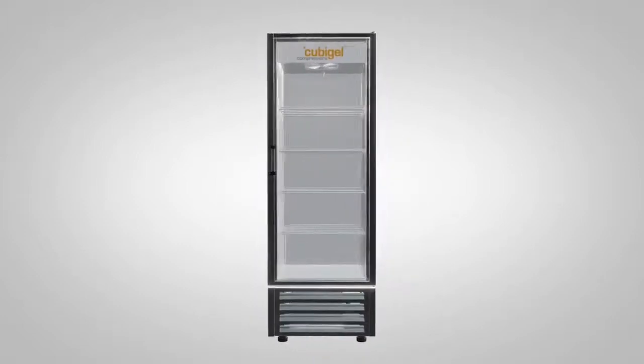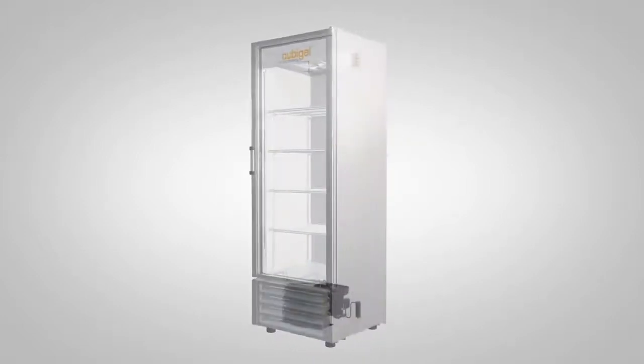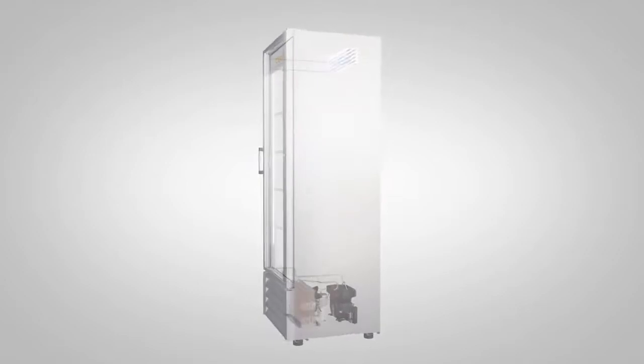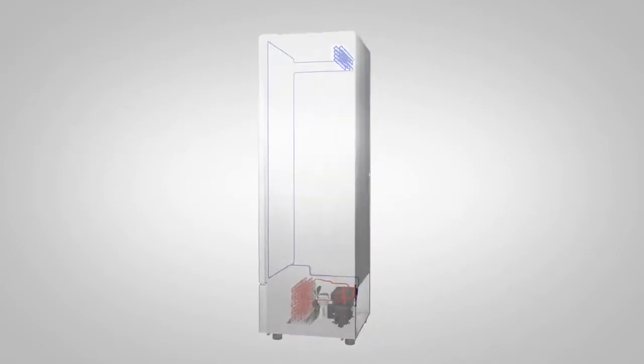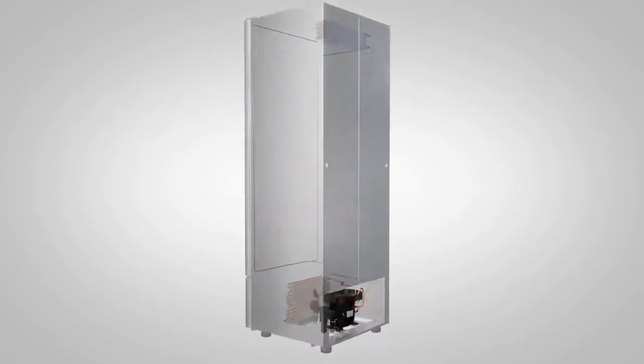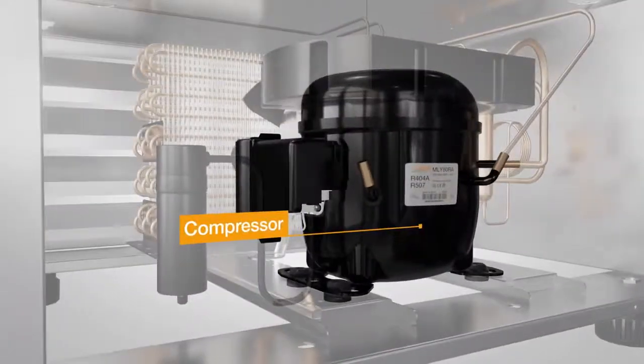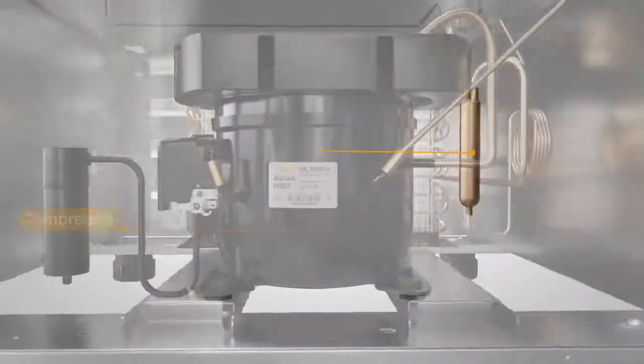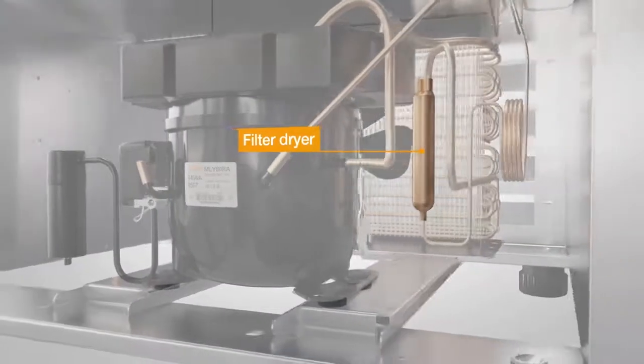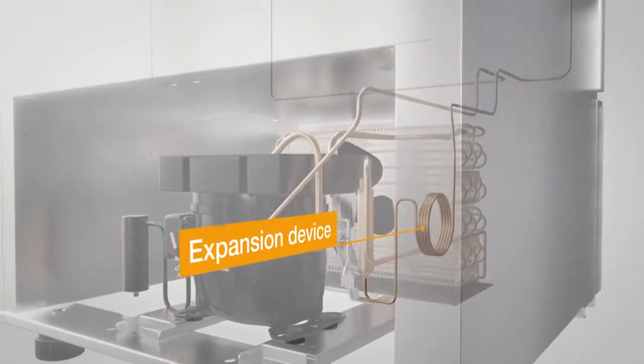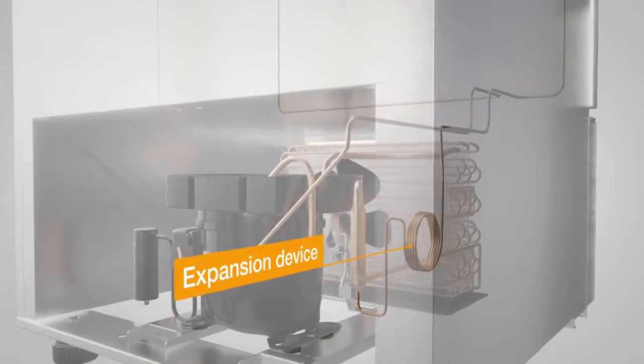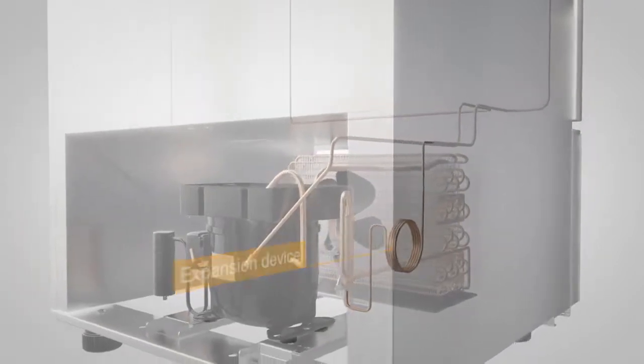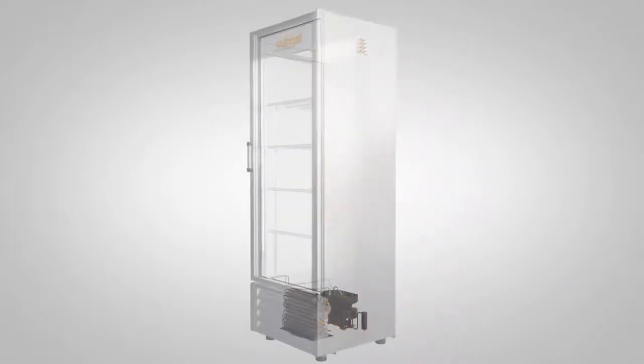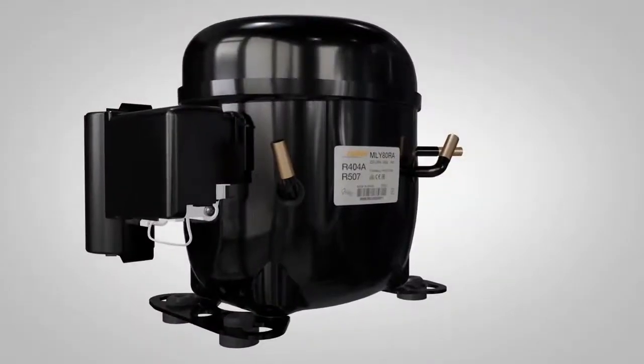To convert a commercial refrigeration system that uses HFC refrigerant to propane, as well as change the refrigerant charge, we must replace the compressor, filter dryer, and expansion device, which can be an expansion valve suitable for the R290 or in our case a capillary tube. To change the original compressor, the first thing that we have to do is determine the equivalent propane compressor.